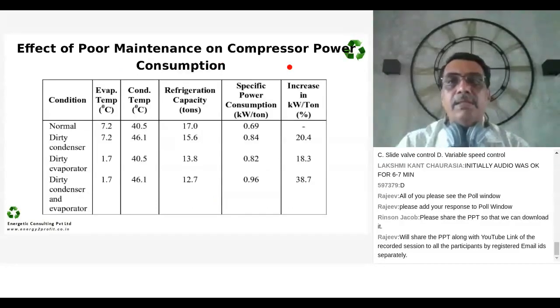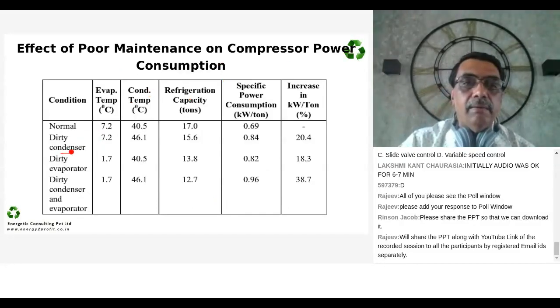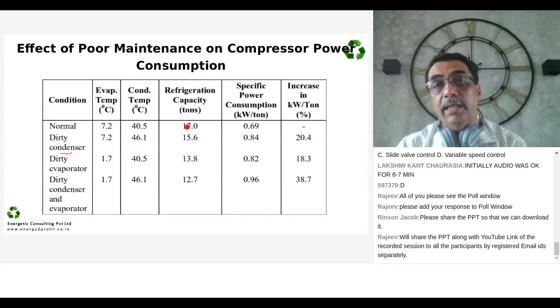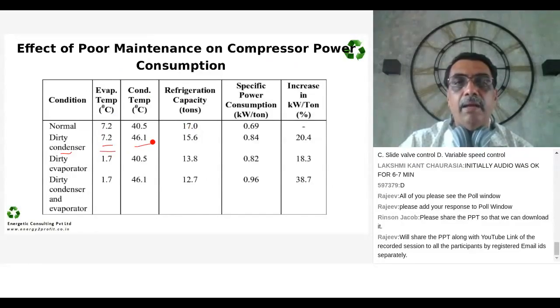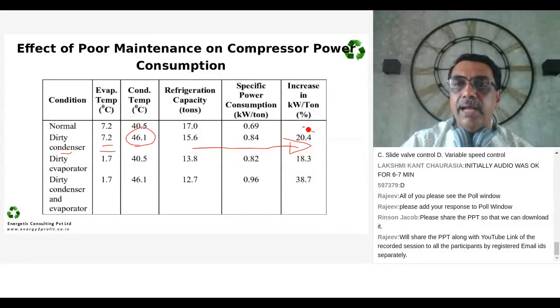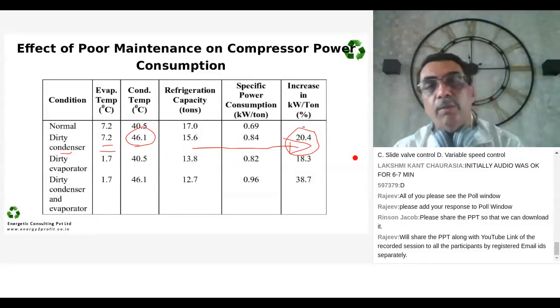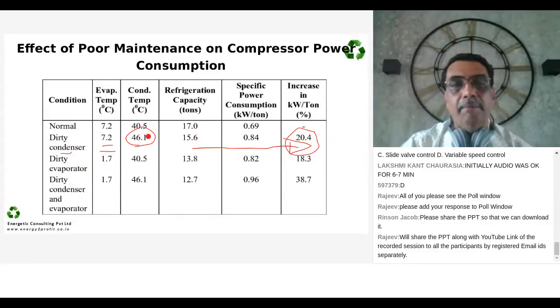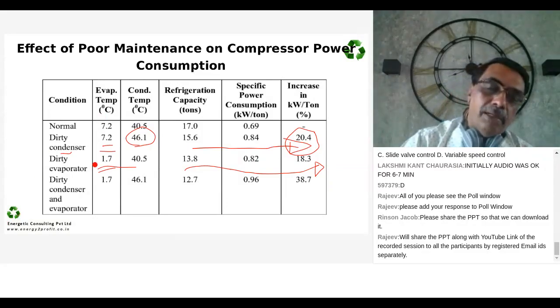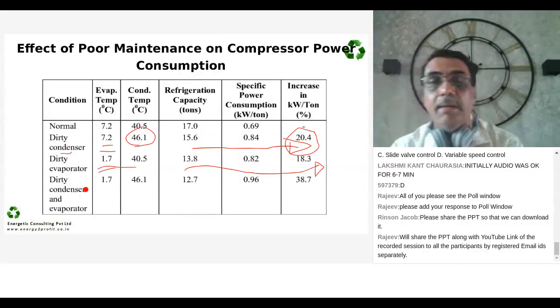Poor maintenance of compressor on power consumption. If you have a dirty condenser but healthy compressor, a healthy evaporator, your evaporating temperature remains same, condensing temperature goes up, and the refrigeration capacity reduces and power consumption increases. You can see power consumption has gone up, and that is as bad as 20.4%. So you are losing 20% of energy because of dirty condenser, in a nutshell. Around 5 degree rise in temperature. On a dirty evaporator, the same thing is around 18%. So around 5 degree temperature drop in the evaporating temperature also has a similar impact.